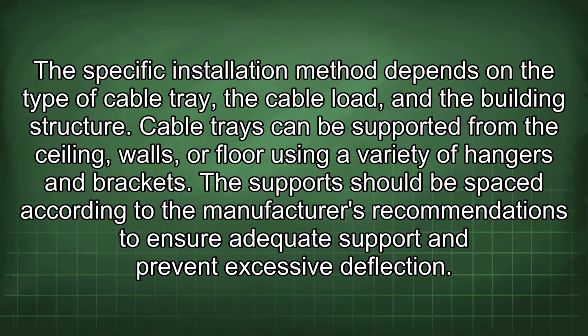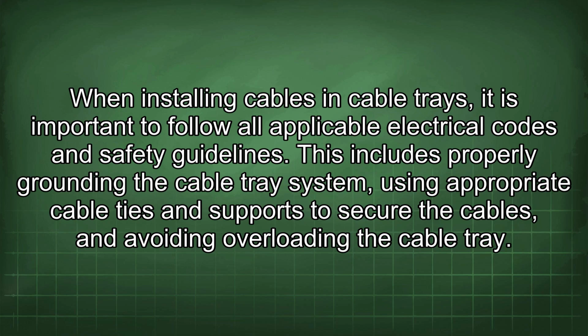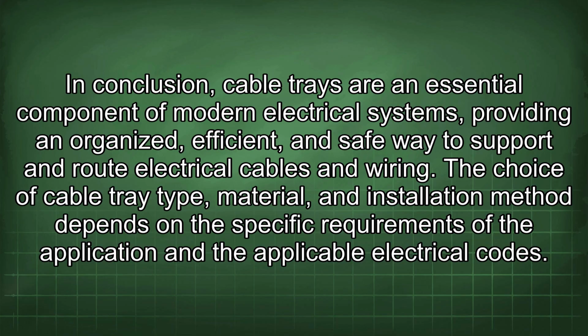The support should be spaced according to the manufacturer's recommendations to ensure adequate support and prevent excessive deflection. When installing cables in cable trays, it is important to follow all applicable electrical codes and safety guidelines. This includes properly grounding the cable tray system, using appropriate cable ties and supports to secure the cables, and avoiding overloading the cable tray.